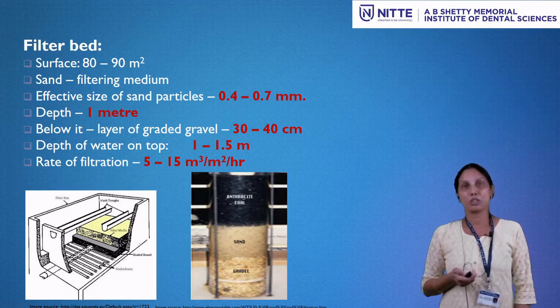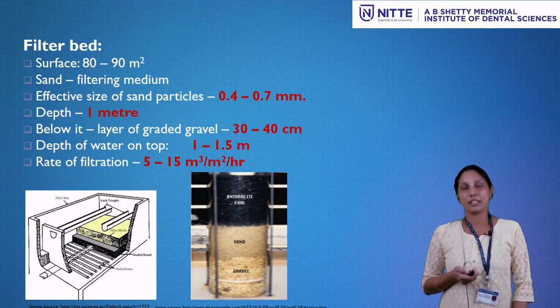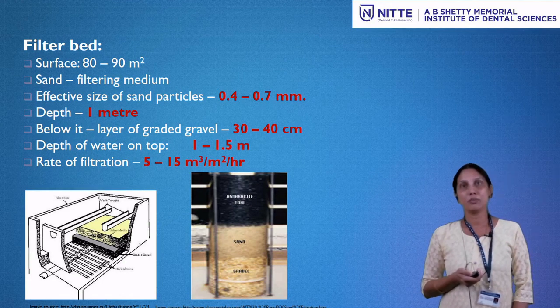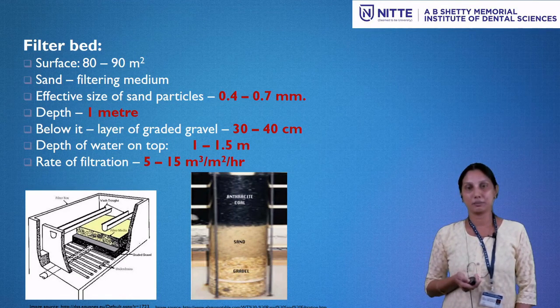The depth of water on the top is 1 to 1.5 meter, and the rate of rapid sand filtration is 5 to 15 meter cube per meter square per hour.